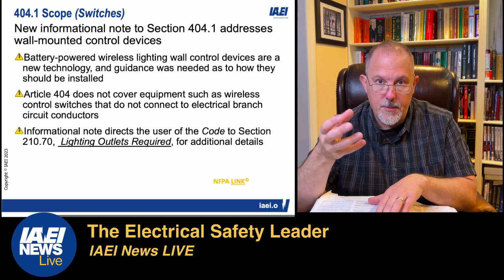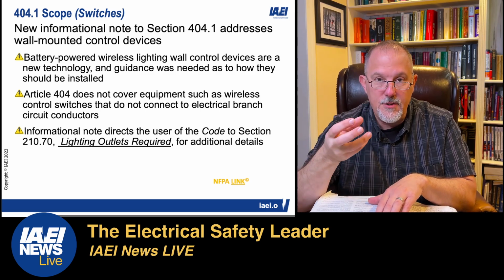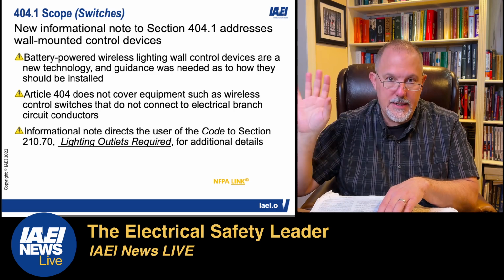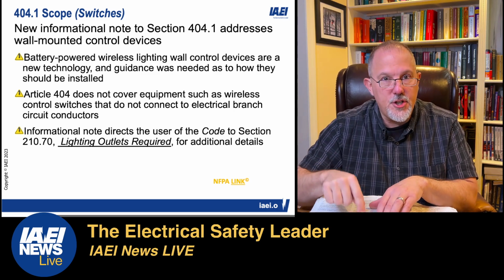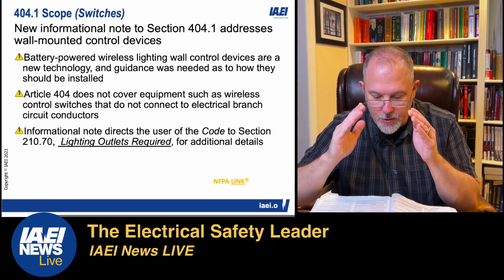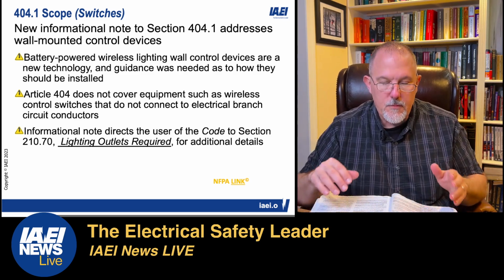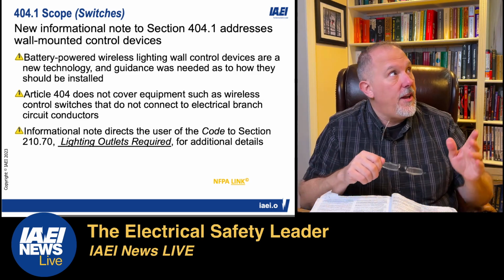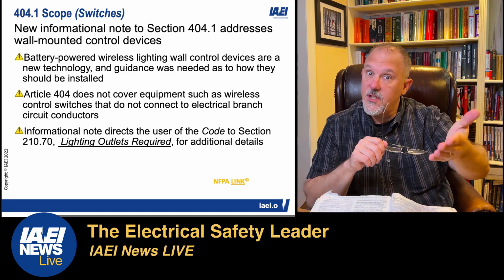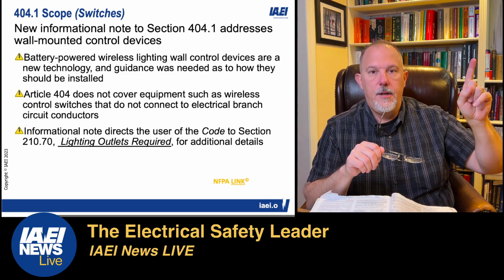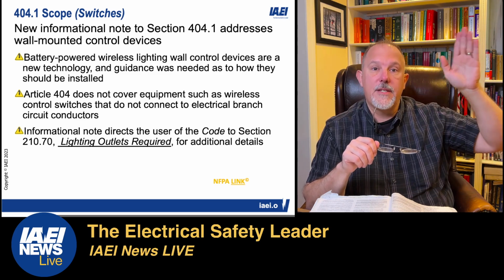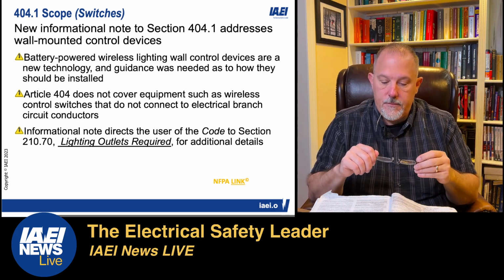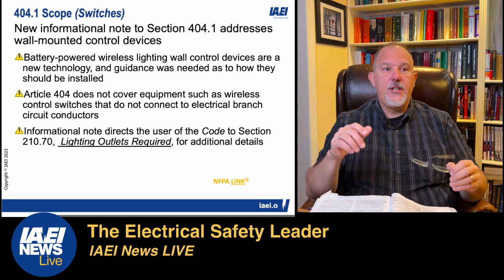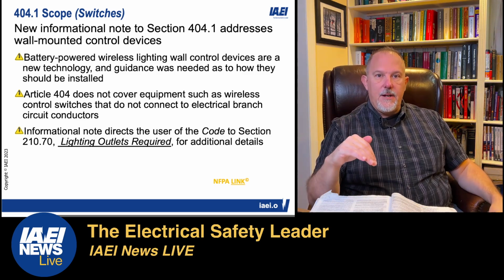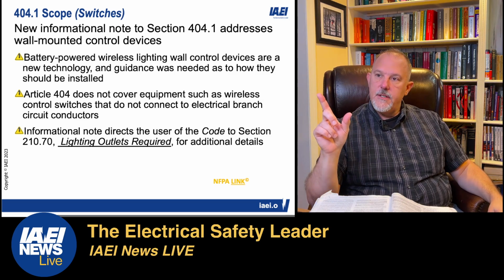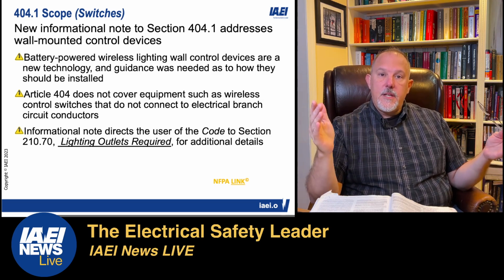So if the lamp or the bulb has the wireless control built into it that is controlled by, say, something you lick and stick on the wall, it would not be permitted because you have to control the outlet. You got to read the words closely. Wall-mounted control. So effectively what you could do, if the unit that is turning on and off the switch is a part of the luminaire built in, then you could wirelessly talk to the luminaire to turn it on and off. Make sense? And I don't have to bring a conductor down to this listed wall-mounted control device, because it would be wirelessly communicating with that switch.